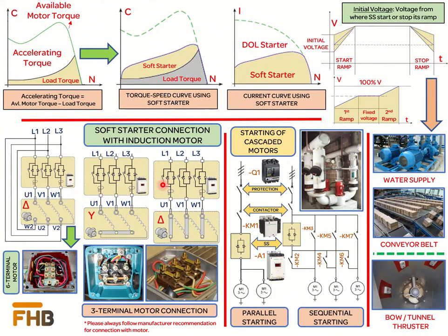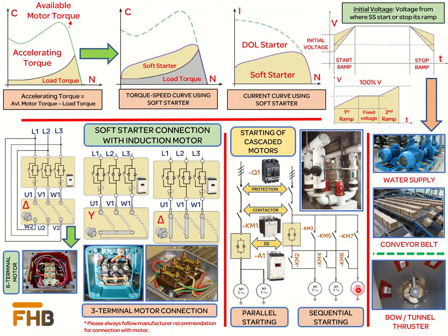Another important area for discussion is the starting of several motors using a single soft starter. These schemes can be divided into two parts. First is the start of parallel connected motors with a single soft starter, as shown in the diagram. Care should be taken that the selected soft starter rating is sufficient to cater to the load and starting current of all the connected motors. The second scheme is the sequential start of motors, called cascaded motor starting, where the soft starter starts the connected motors one by one. Care should be taken that the soft starter rating is sufficient for each connected motor.